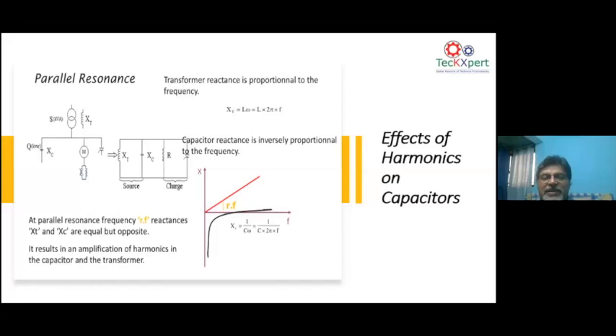So that means when you have a combination of inductance generated by your transmission line or your transformers and inductive motors, all that produces a certain amount of inductance. So that inductive impedance is proportional to the frequency. Now, if you have capacitors in the network, the capacitive impedance is inversely proportional.